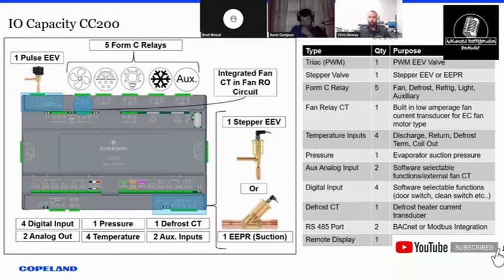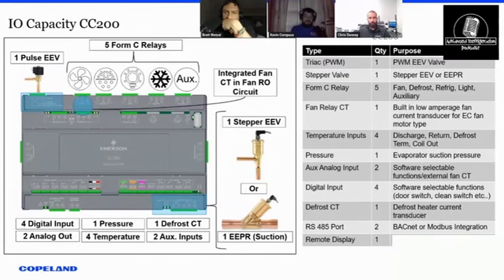That's 1 main alarm. The other one that we do is we look at temperature-based termination. If we see that a defrost was set up for temperature-based termination and it did not terminate on temp, we will throw out a fail to terminate on temp alarm, basically saying, hey, you were supposed to terminate and you didn't for some reason. So those 2 alarms are very powerful if they're used the right way and taken seriously, like you said. The did not terminate alarms are great, but they've always had that nuisance there. But you add that defrost CT in there, and especially the electric defrost, and you're basically stopping all those midnight service calls. Yeah, that's the hope.